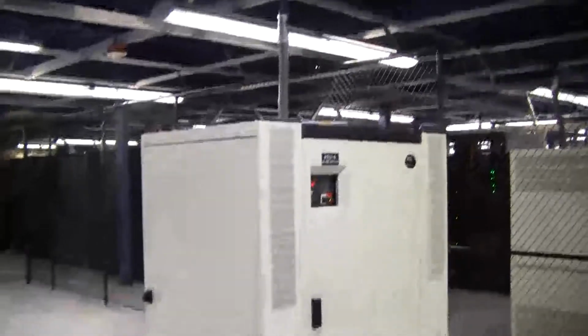We provide redundant circuits to each customer cabinet. So say a customer wants to come in here, we provide an A circuit and a B circuit. The A circuit would come from one PDU, the B circuit would come from like PDU 6. Each of these PDUs is set up onto two different UPSs, one goes to UPS 1, one goes to UPS 2.